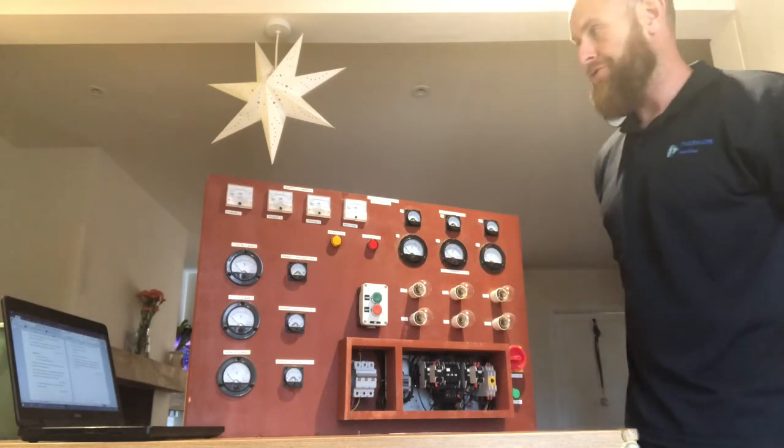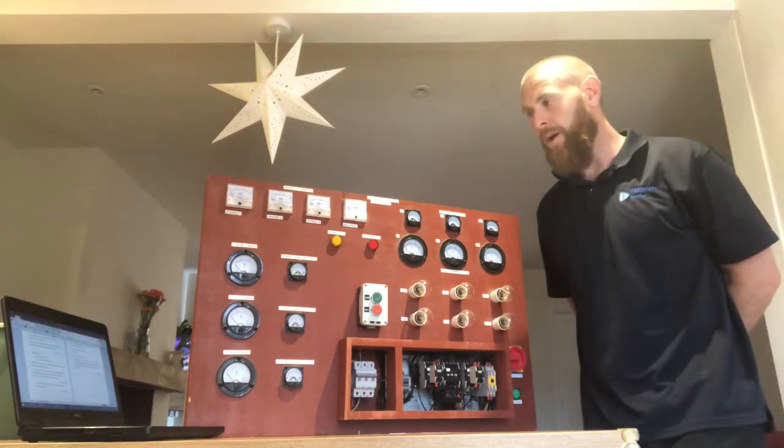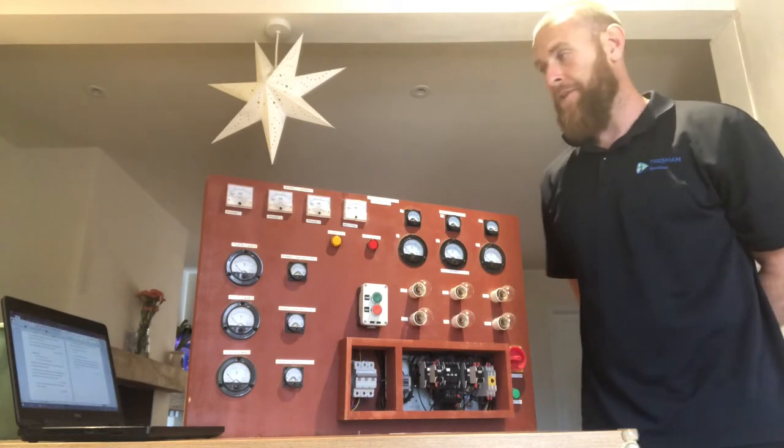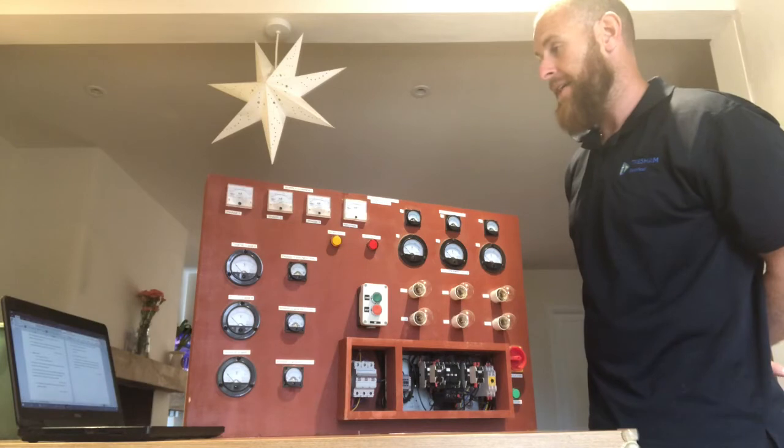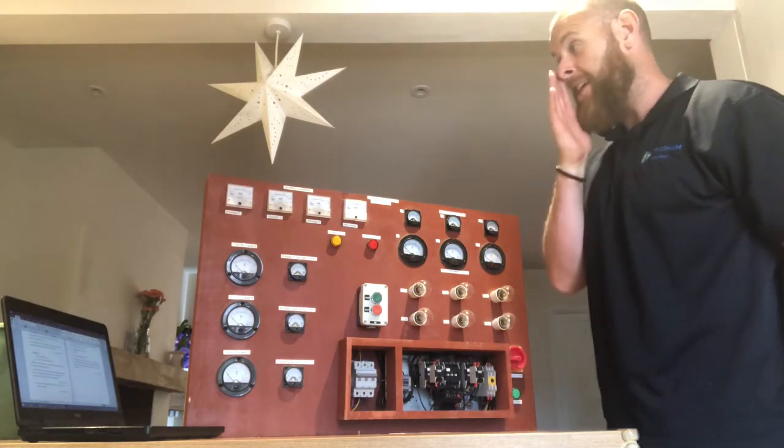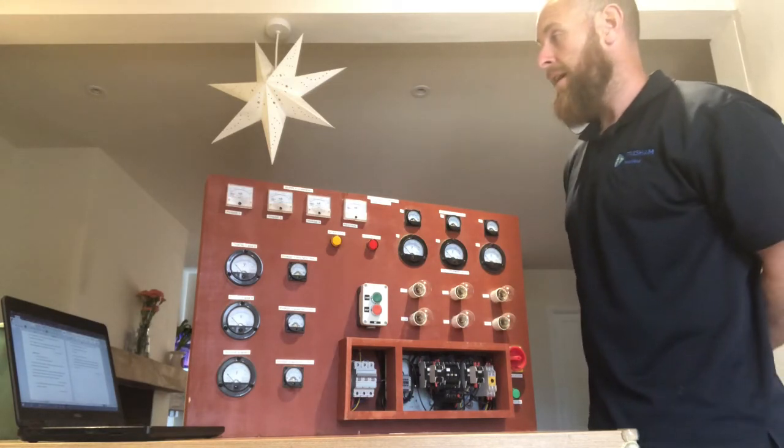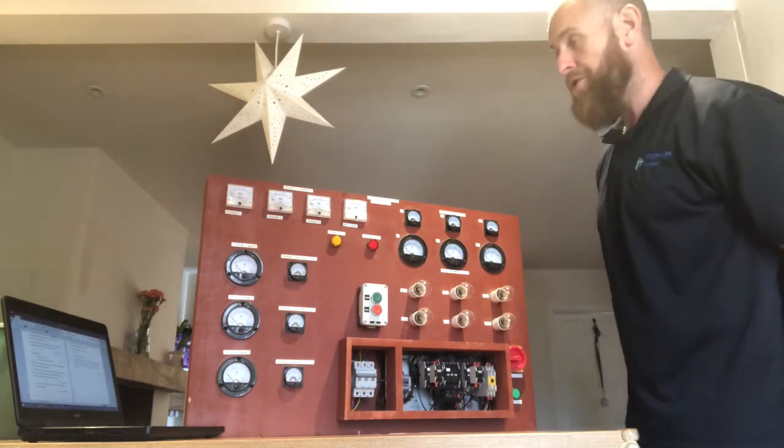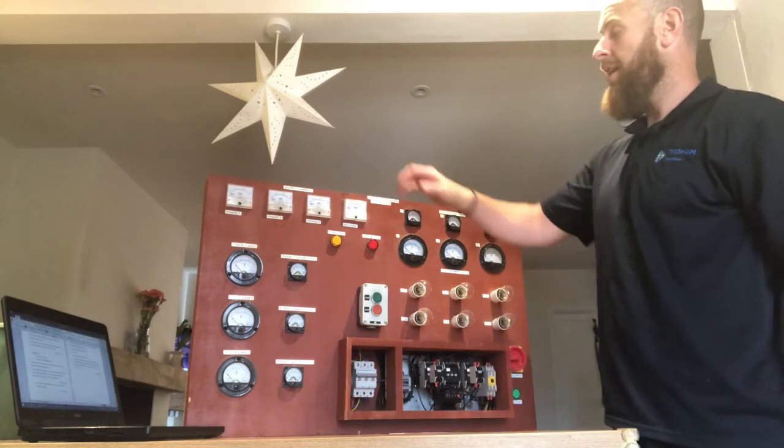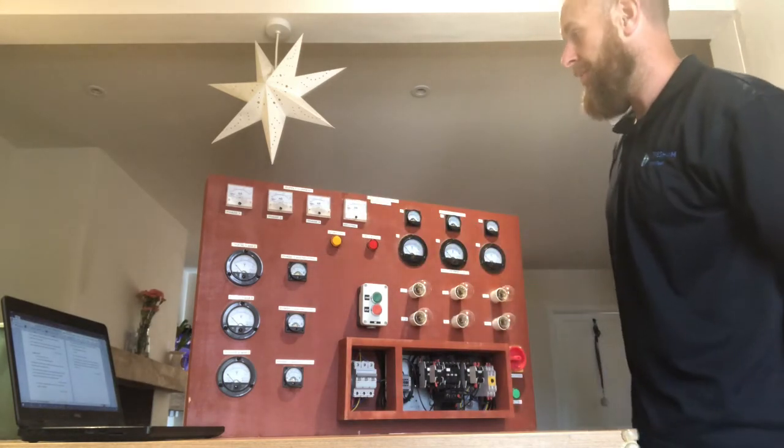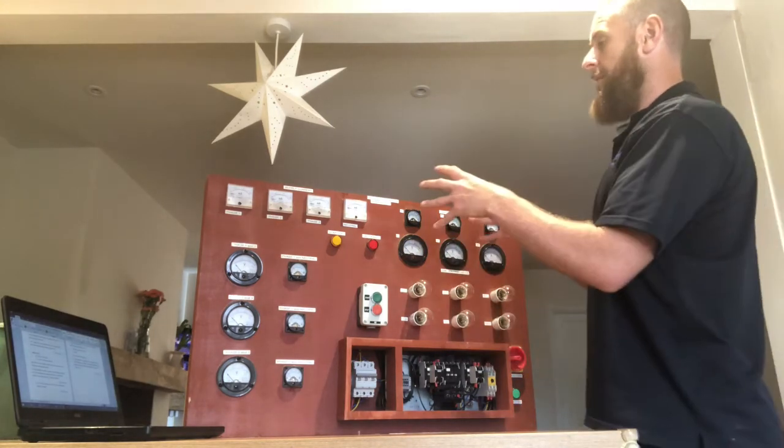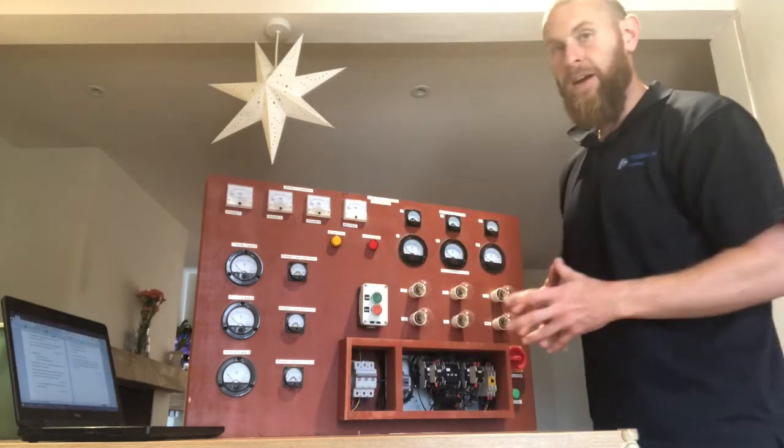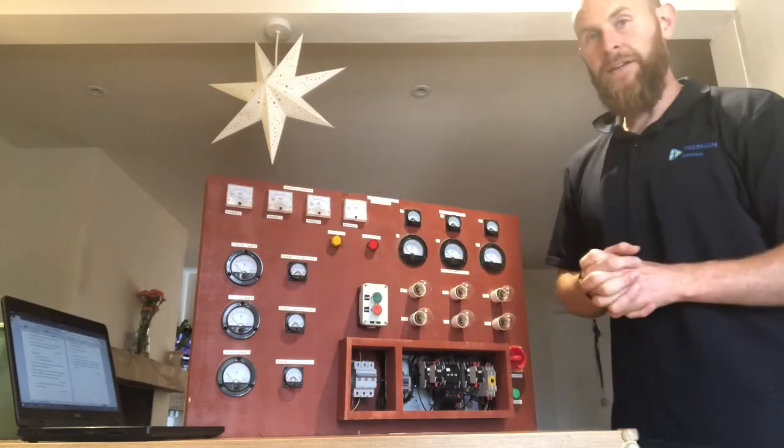One of the questions is how does this comply to the electrical regulations. So the regulations that we work with are BS 7671, at present that is the 2018 version, so they came out in 2018 and it's known as the 18th edition. Various regulations in there are to do with prevention of electric shock and that's in part four. So what's really important is we have what's called IP rating, index of protection. What that basically means is that I must not be able to get my fingers in contact with any of the live parts.